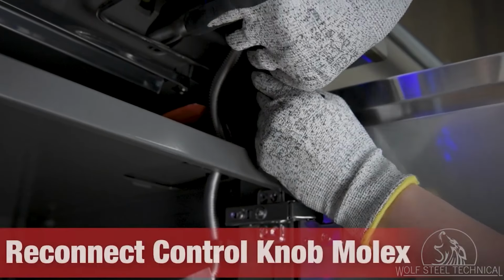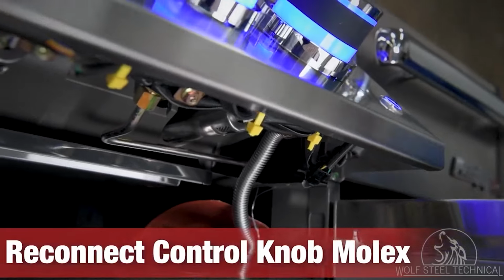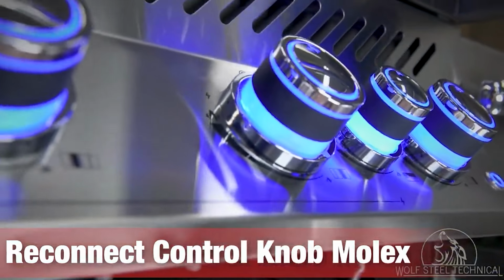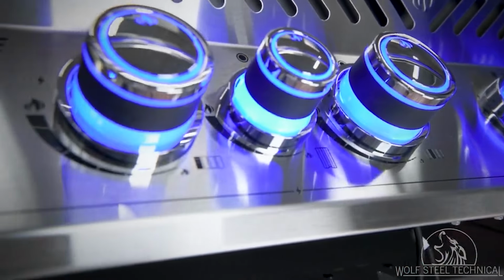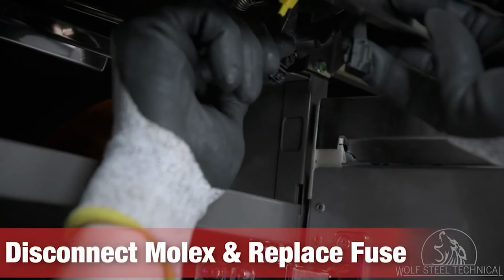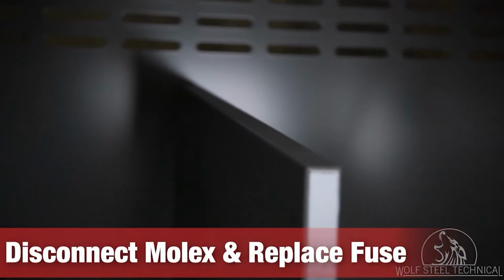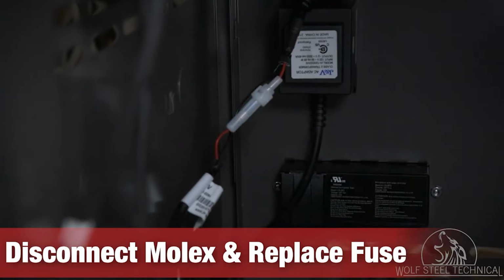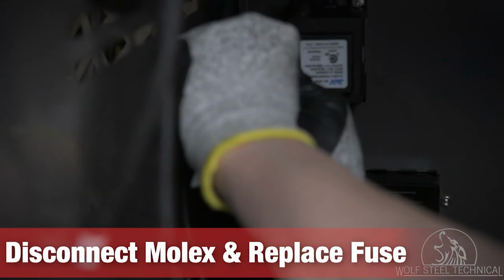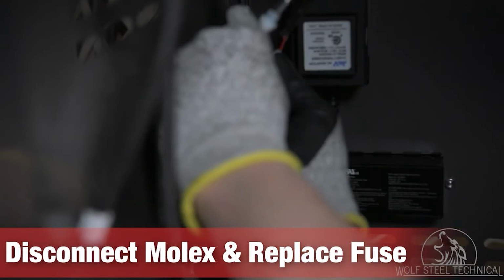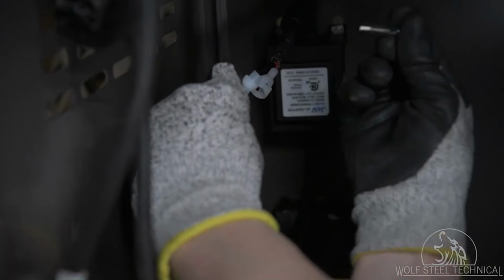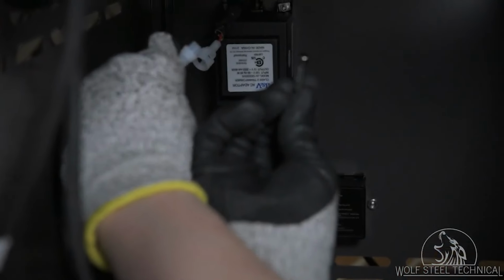Next, reconnect the black Molex on the right. In doing this, the control knob lights should come on. If the lights don't come on, disconnect the black Molex and replace the fuse. The fuse is located within the white casing on the power wire harness. It can be accessed by pressing into the center and twisting to open and close it. Do not touch the fuse with your bare skin, as it will lead to premature failure.